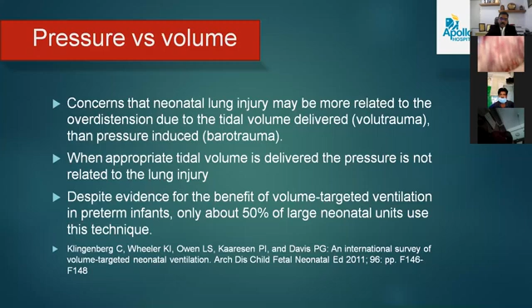Despite evidence for the benefit of volume targeted ventilation in preterm infants, this is one thing which I really want all our people to emphasize: all of us know that volume ventilation is very good, volume ventilation is the way to go forward, but even in international and worldwide statistics, it's only around 50% of the large neonatal units that use this technique. Probably this percentage should change in future. So as you see, the advantage of pressure versus volume control is depicted in this graph: with the improvement in compliance in pressure limited ventilation, the delivered volume increases.